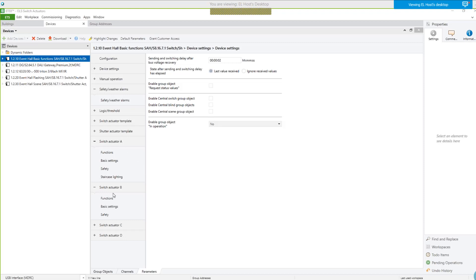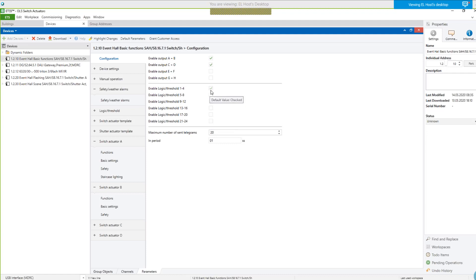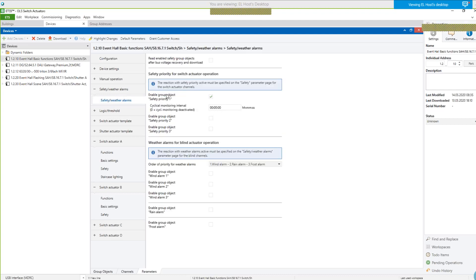We need two switch actuator channels, A and B. Channel A is the entrance area — this is staircase lighting. Switch actuator channel B is linked to the exit lights. I have configured four outputs, but at the moment I need only two: A and B. I have programmed a logic threshold function — I need one logic out of 24 available. I have also programmed safety functions: safety priority one for fire alarm, which is the highest priority and turns on all lights. Safety priorities two and three are available but not used here — not enabled.